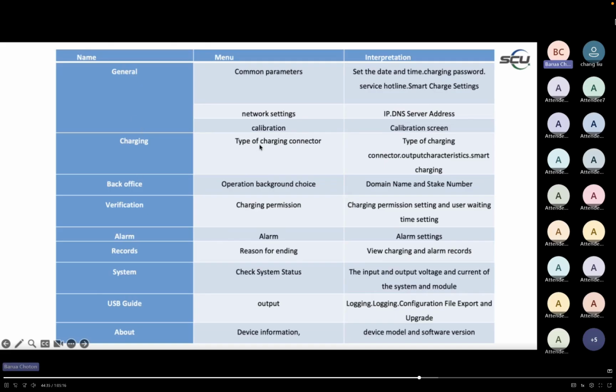In the charging tab, we can define the types of charging connector. If it's a dual CCS2, that's already factory settings, but in future if you decide to change from CCS2 to CCS1, you change the cable and also have to define the protocol for that individual gun, making the settings under the charging tab. Also, if you want to put limitations - say you have 300 ampere on two cables and want to make one of them 150 - you go to charging, and under smart charging you can limit the current the cable gets.